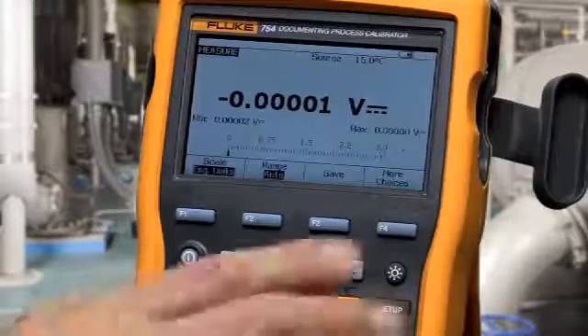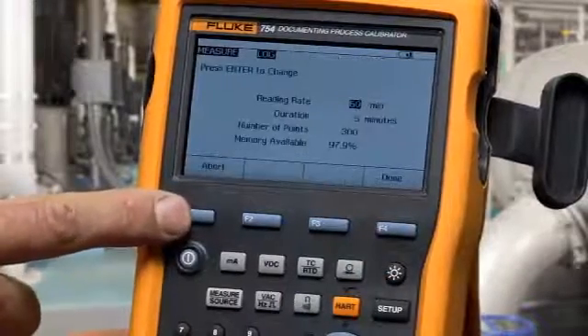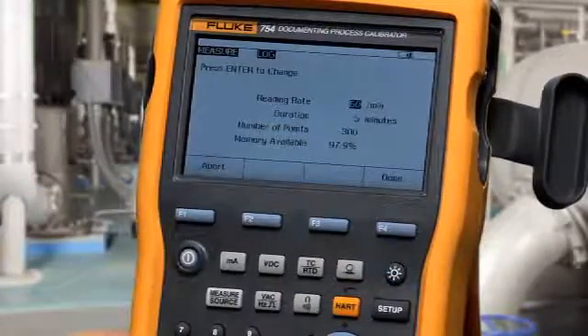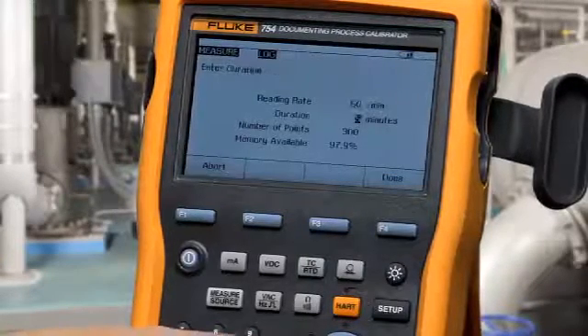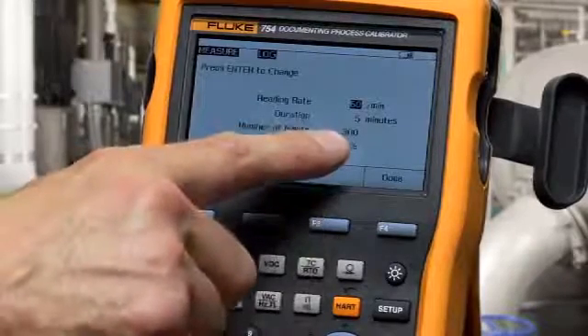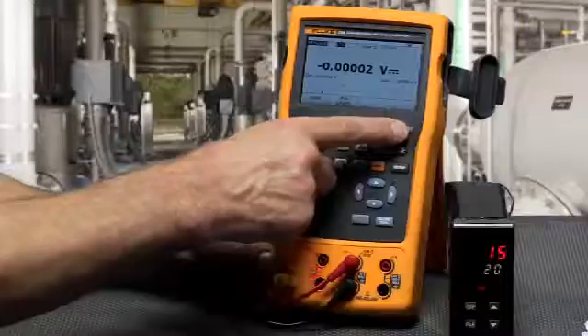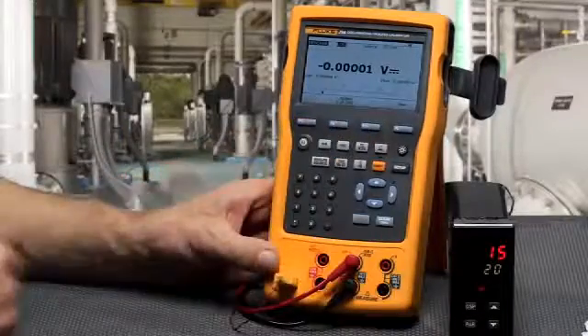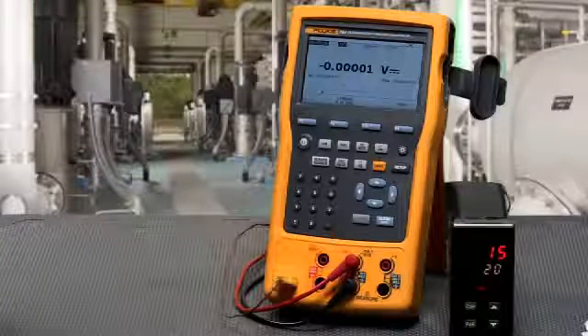To do logging measurements, select more choices, select log, enter the number of points that you want to log, say 60, the number of minutes, and that calculates the number of points based on that reading rate over that period of time, done, and then start logging, and it will log those measurements to memory so you can upload them later to a PC.